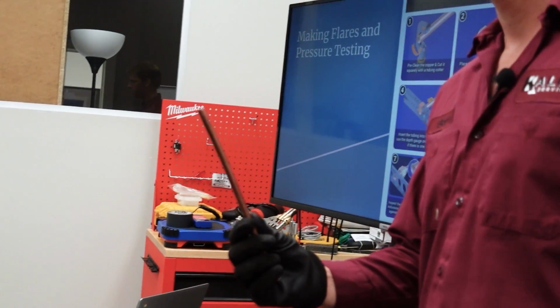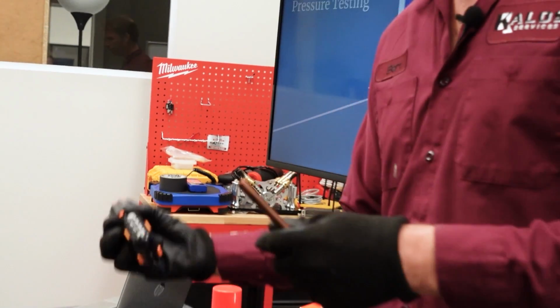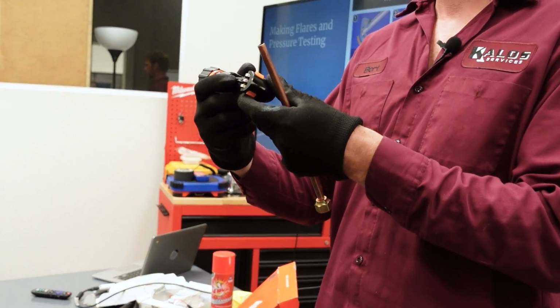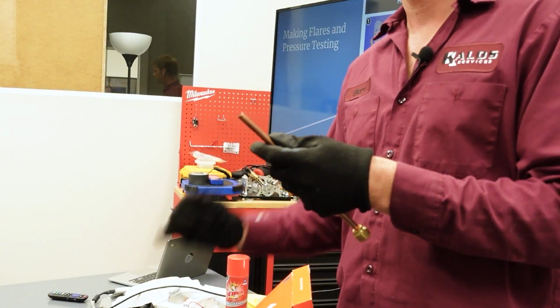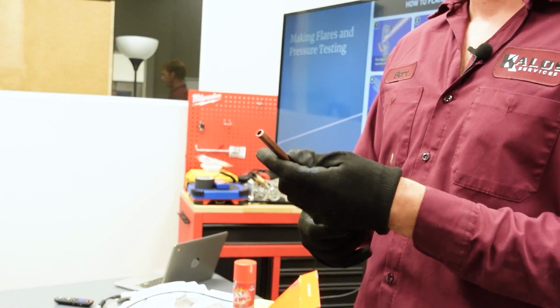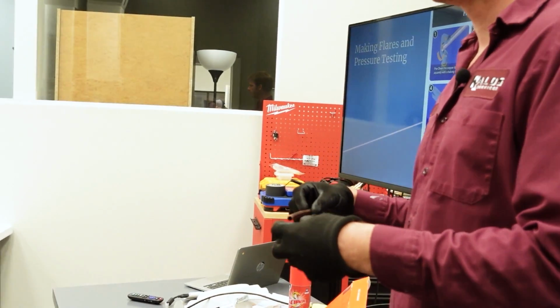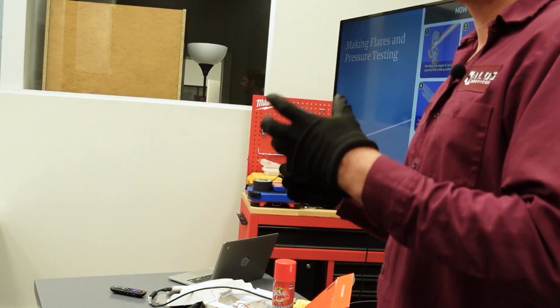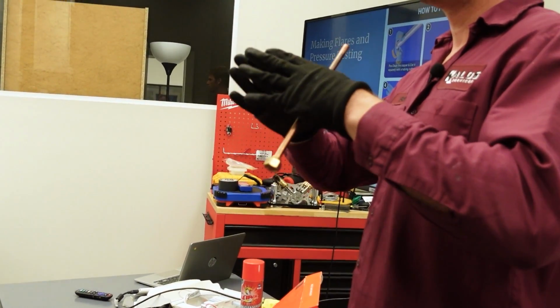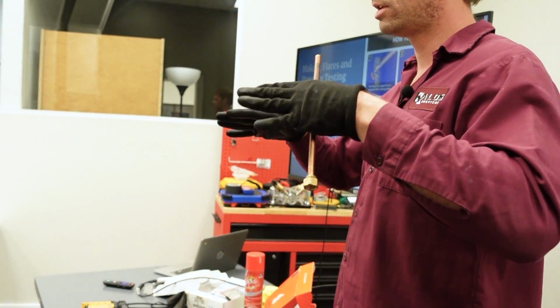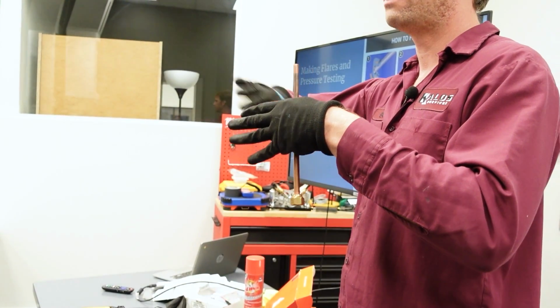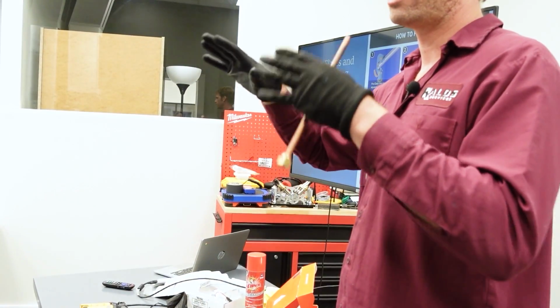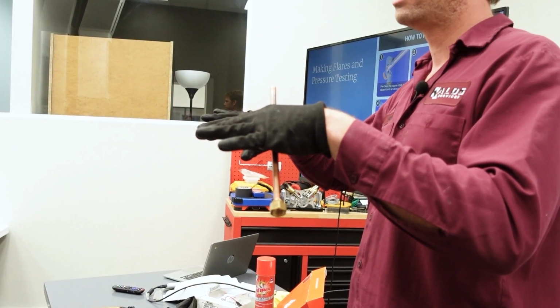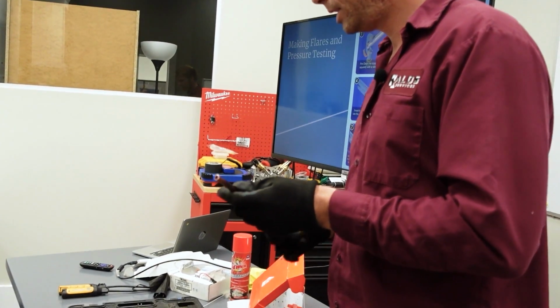When you're cutting copper, the blade pushes into the copper to form that cut, so you get a little lip on the inside that curves over. If you just stick that straight into your flare tool and push it out, that lip gets smashed, and on the inside of your flare there's going to be ridges and cracks, which is a point where you can actually have leaks.